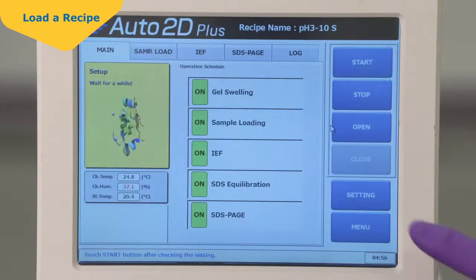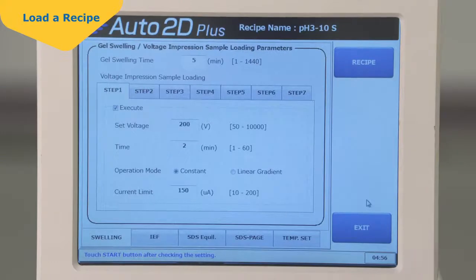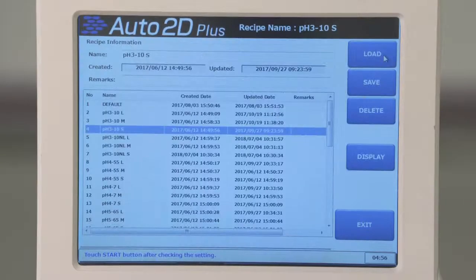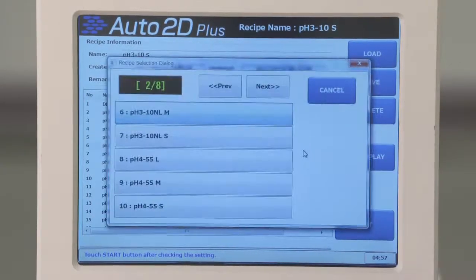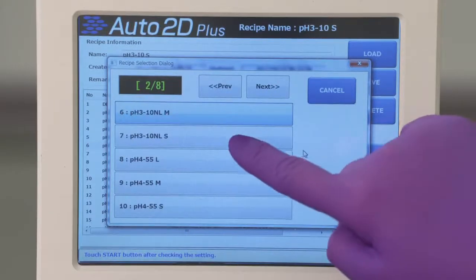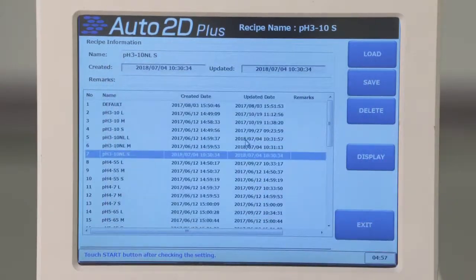You can view standard recipes by touching settings, then recipes. Touch the recipe information screen and a recipe selection box will appear. Select an appropriate recipe for the pH range of your IEF chip. Touch Load to load the recipe.